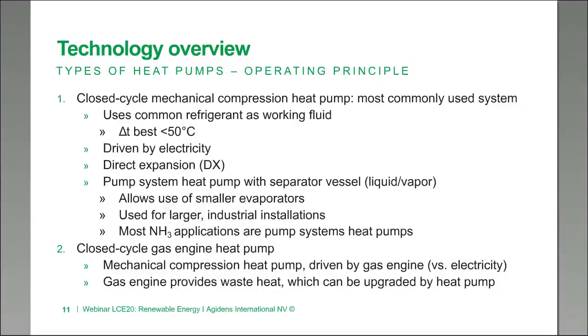Pump systems allow the use of smaller evaporators because they focus on the gaseous form only. These pump systems are usually used for larger industrial installations. Most ammonia applications tend to be pump system heat pumps. Another type is the closed cycle gas engine heat pump, very similar to the mechanical compression heat pump but with the compressor driven by a gas engine rather than electricity. The combustion engine also generates heat, which can be used as a source heat and upgraded by the heat pump towards a destination point.